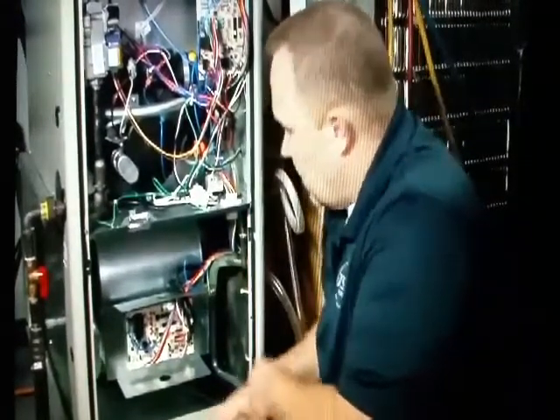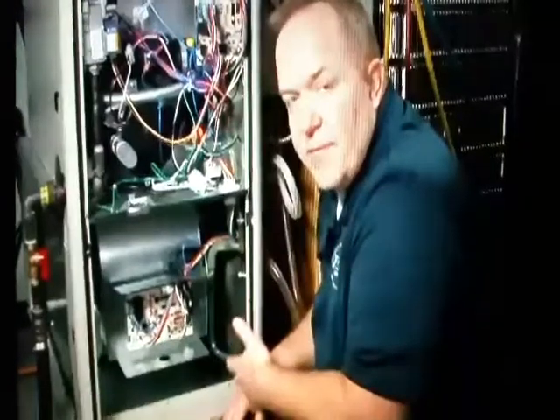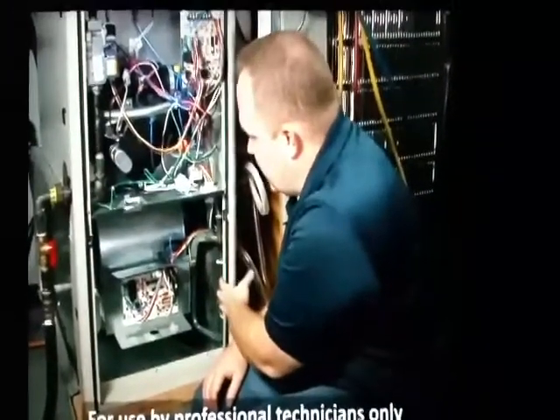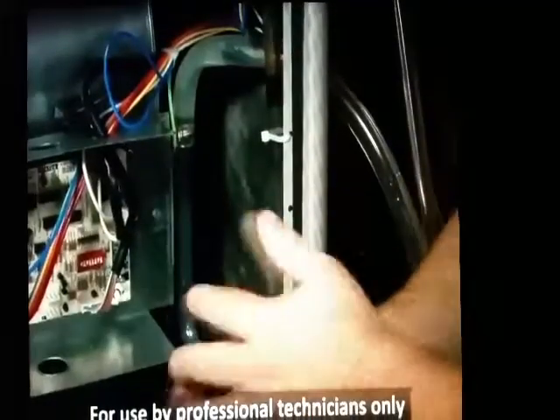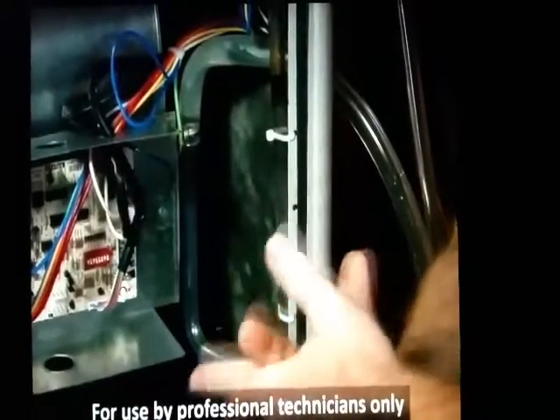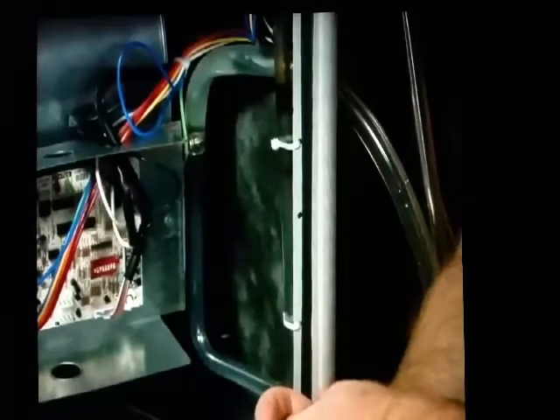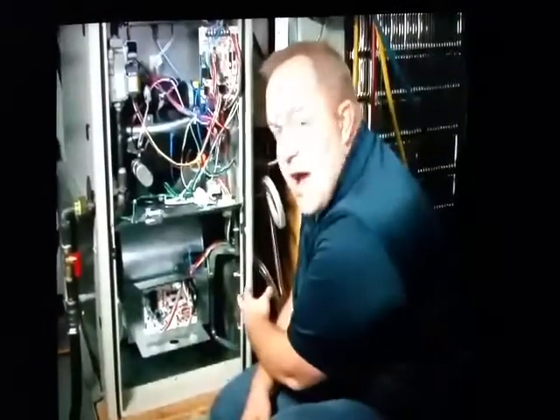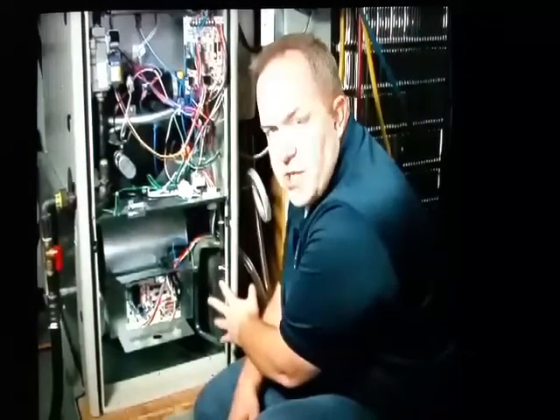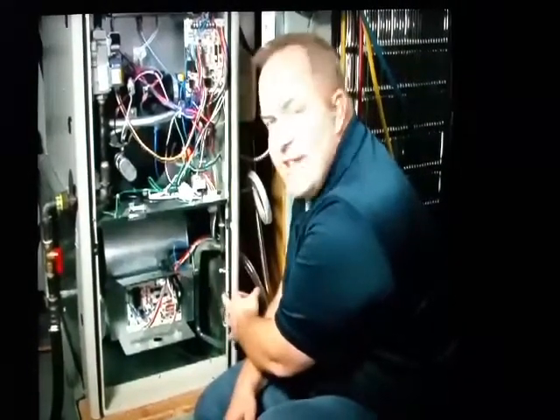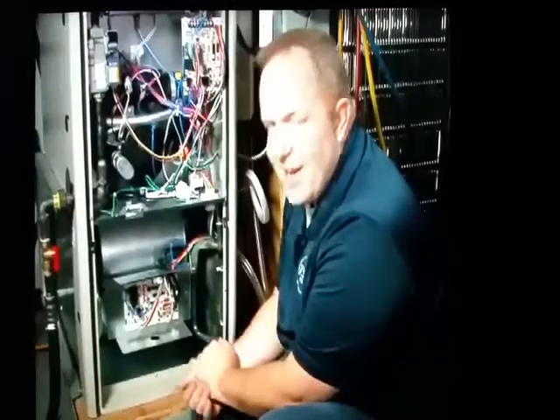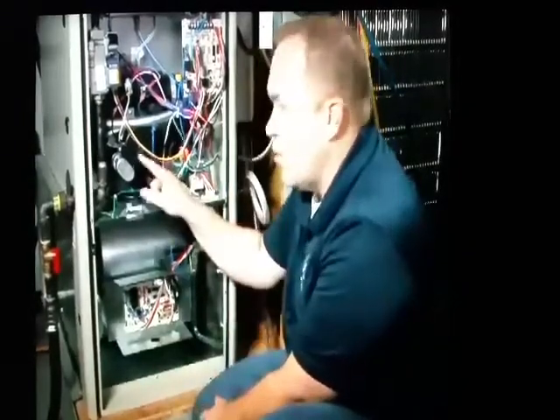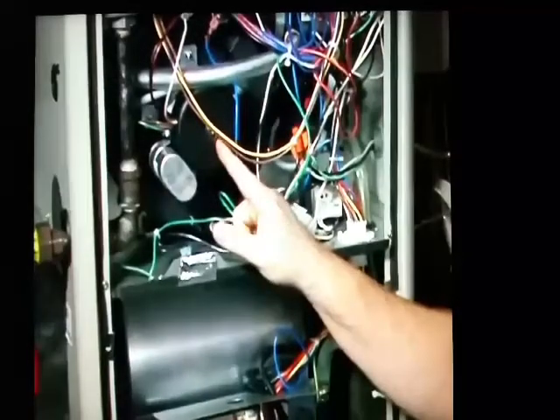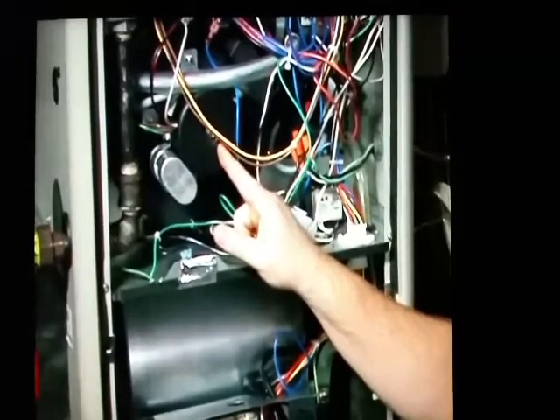Have you ever looked inside of a high efficiency gas furnace and seen a trap assembly and wondered to yourself, what actually is the purpose of the trap? The trap in high efficiency heating ultimately acts as a vacuum break against the negative pressure, or the suction, if you will, that's being generated by the inducer assembly.